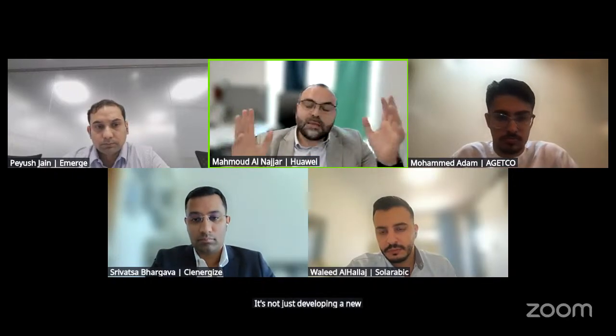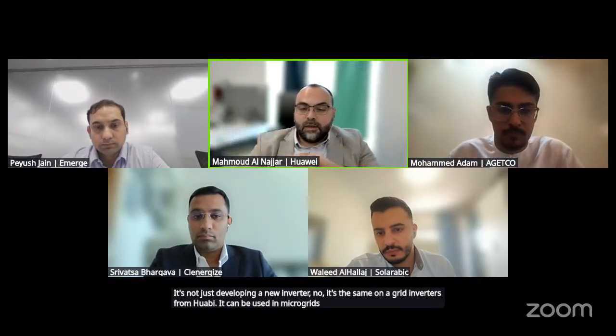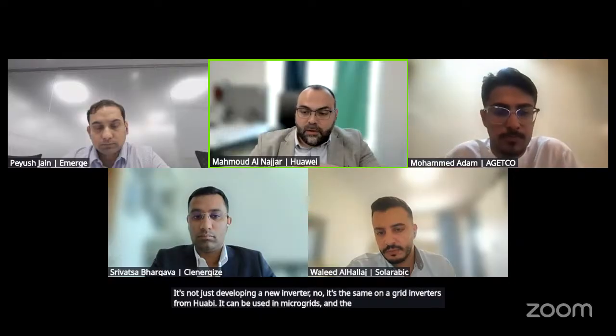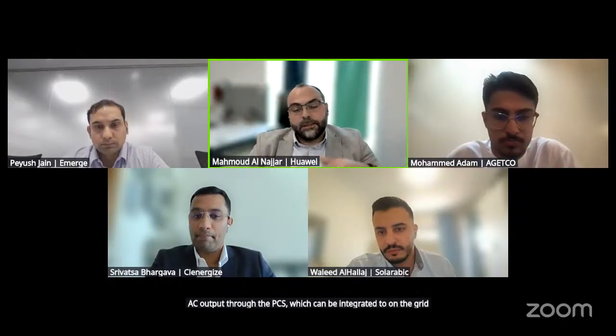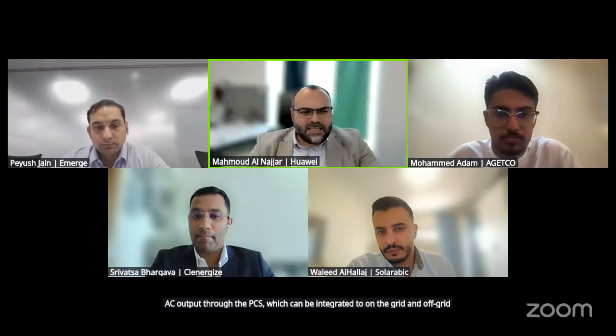It's not just developing a new inverter. No, it's the same on-the-grid inverters from Huawei. It can be used in microgrids, and the batteries have AC output through the PCS, which can be integrated to on-the-grid and off-the-grid. So as I said, it's much more scalable, and it can be fully utilized in better ways than a DC coupled system.